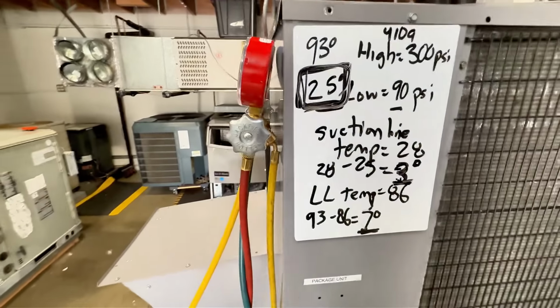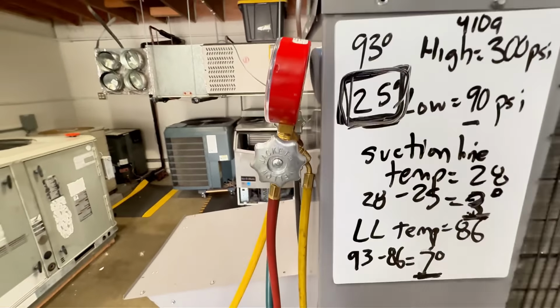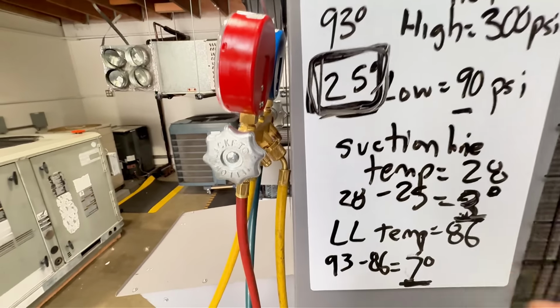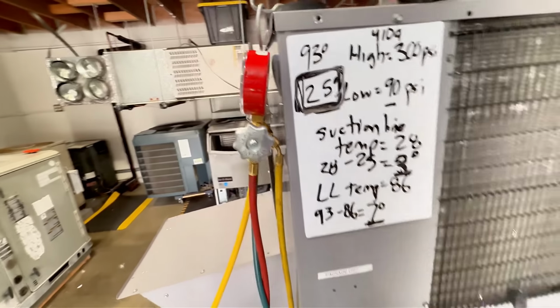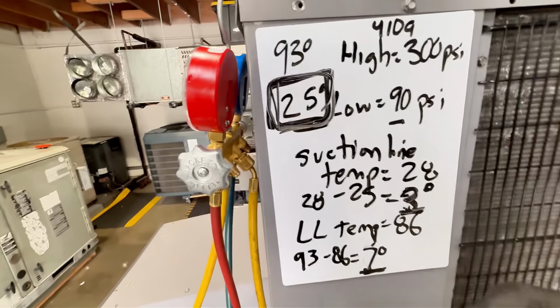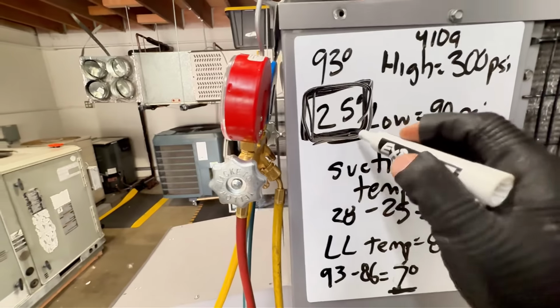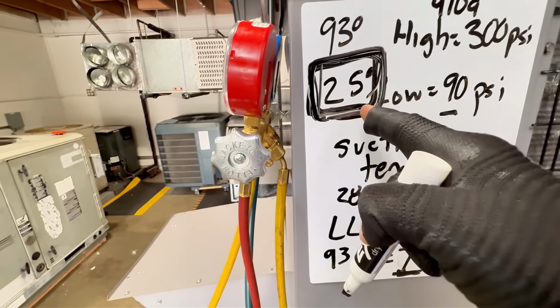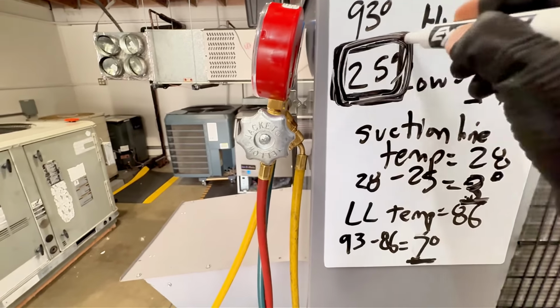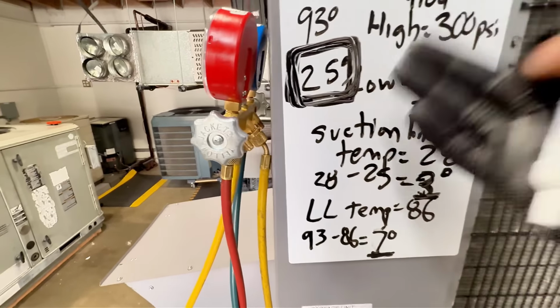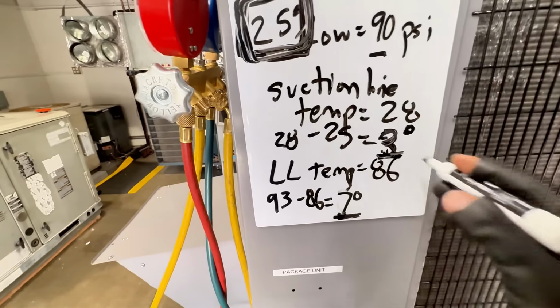Okay. Now I can feel way more airflow coming out. So now look at the numbers change, okay? Wherever you're at, because I'm going to have to erase this, try to just memorize these numbers. You can write them down somewhere, but my evaporator temperature with low airflow was at 25 degrees, and my superheat was 3.